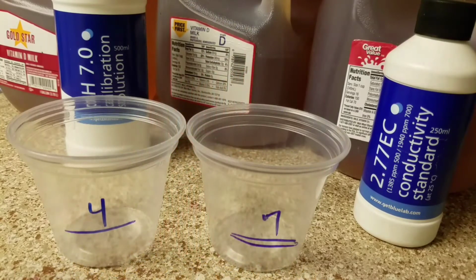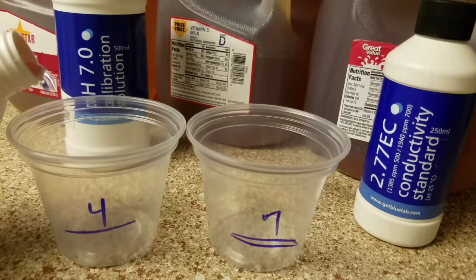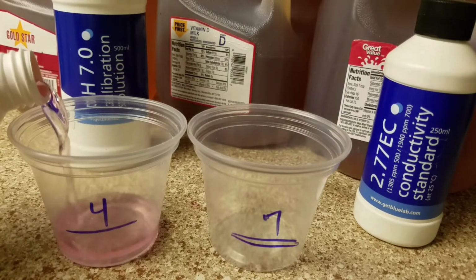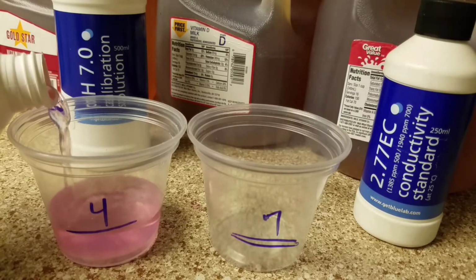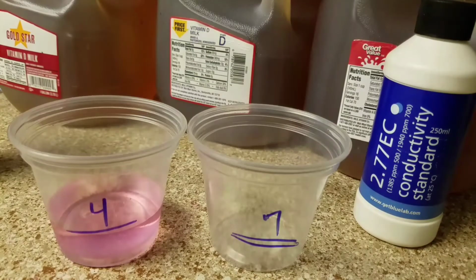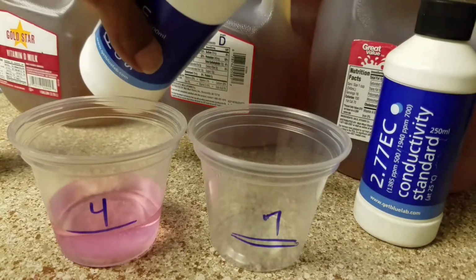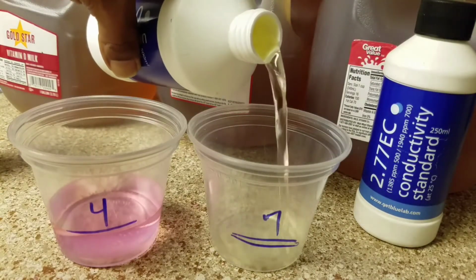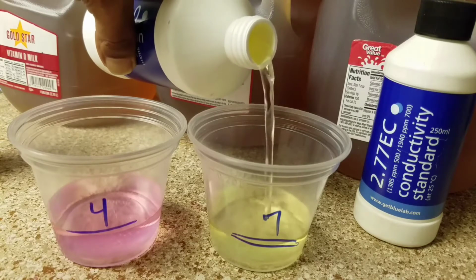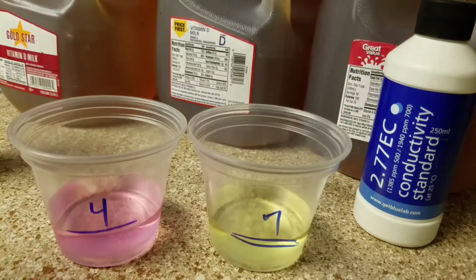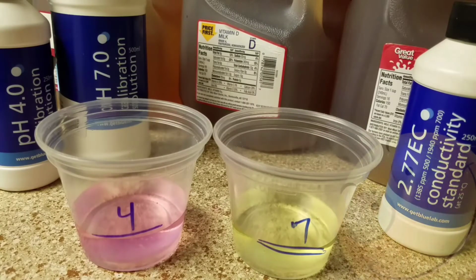Side note, I went back and put a little fill line right there, so I know I'm going to touch the probe unit with the liquid. So I'm going to go ahead and pour the 4 in here up to that point. This is a little better with shot glasses because you don't have to use as much liquid. One thing I do want to point out is the liquid that is pink is the calibration number 4 solution, and the liquid that is yellow is the calibration number 7 solution. So now that we have them poured up, let's get to calibrating.